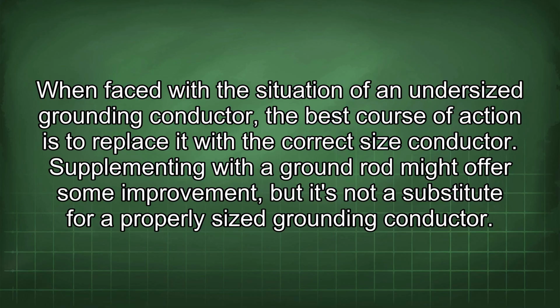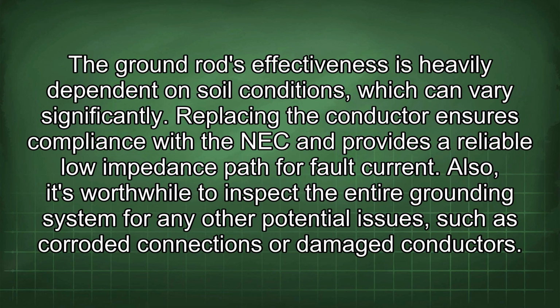When faced with the situation of an undersized grounding conductor, the best course of action is to replace it with the correct size conductor. Supplementing with a ground rod might offer some improvement, but it's not a substitute for a properly sized grounding conductor. The ground rod's effectiveness is heavily dependent on soil conditions, which can vary significantly. Replacing the conductor ensures compliance with the NEC and provides a reliable low-impedance path for fault current. Also, it's worthwhile to inspect the entire grounding system for any other potential issues, such as corroded connections or damaged conductors.